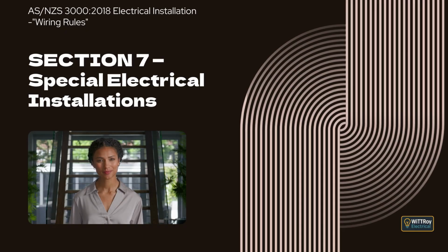The clause then explains that these fire and mechanical protection requirements do not apply where the wiring is already installed in a location or enclosure that provides protection, or where circuits provide the primary power source to fire detection and alarm systems that have compliant battery backup up to the control and indicating panel, or for circuits supplying emergency warning systems beyond the main equipment panel when they comply with the relevant standards.